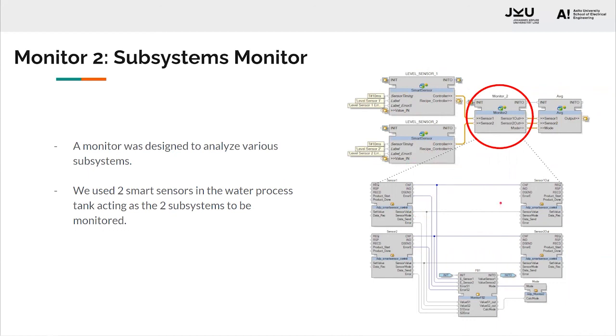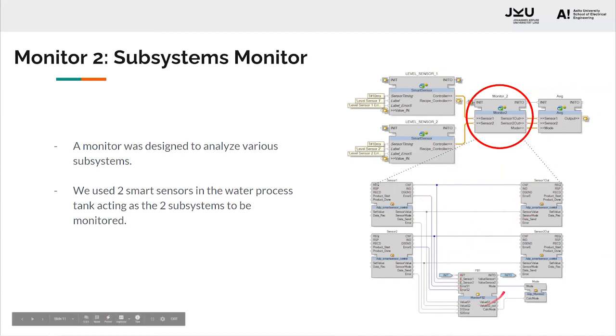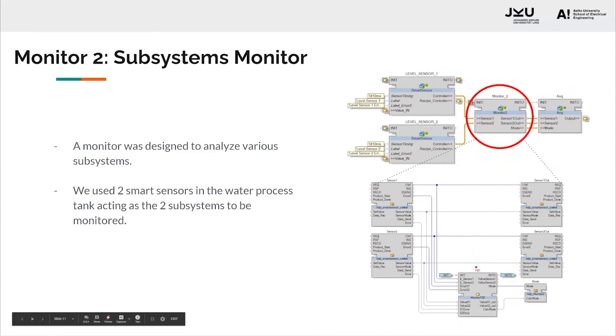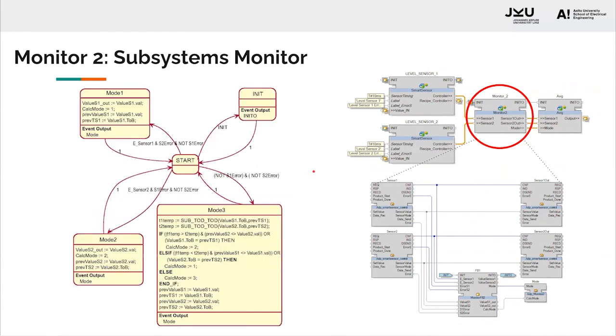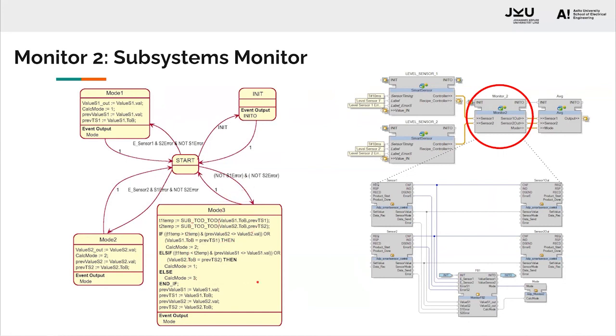Here we can see the composition for monitor two. Information from each sensor is directly passed ahead without any modifications. What the monitor does is take the inputs and monitor the condition and then send a value to the average FB. What it monitors can be seen in the state machine. It checks for sensor errors. So, as we said before, the smart sensors are capable enough to inform if they're in a state of error. So if none of the sensors are in error, the monitor basically runs in mode three, which is using the average of both the sensor values.